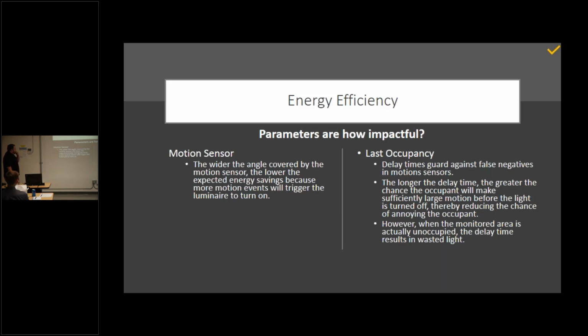So, the first is occupancy and motion sensors. The wider the angle covered by the motion sensor, the lower the expected energy savings, because more motion events will trigger the luminaire to turn on when it's not necessary, i.e. someone just walking by a cubicle, the sensor picks them up, and it turns on. So if you narrow that field of view to be within the cubicle or the workspace area, then people walking by won't trip it as often.